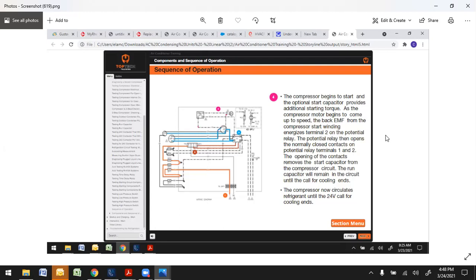If you have lights that are dimming sometimes, usually the addition of a start component will reduce the lights dimming. As the compressor motor begins to come up to speed, the back EMF from the compressor start winding energizes terminal 2 on the potential relay. At that point, the potential relay will open up and drop out your start capacitor.